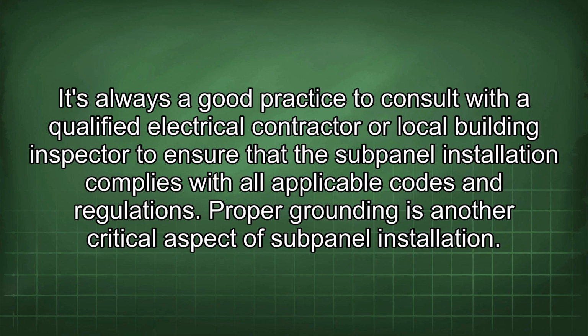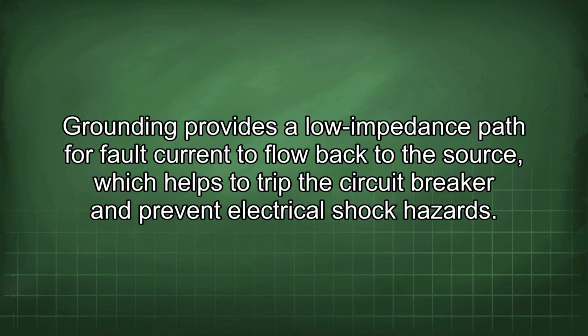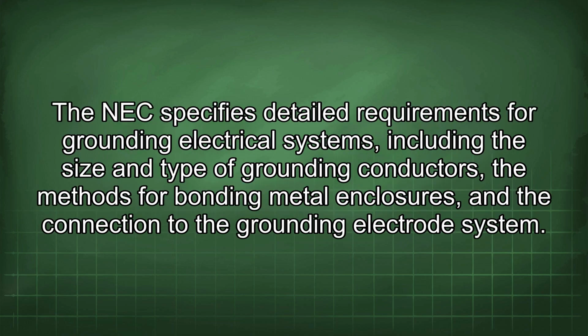Proper grounding is another critical aspect of subpanel installation. Grounding provides a low impedance path for fault current to flow back to the source, which helps to trip the circuit breaker and prevent electrical shock hazards. The NEC specifies detailed requirements for grounding electrical systems, including the size and type of grounding conductors, the methods for bonding metal enclosures, and the connection to the grounding electrode system.